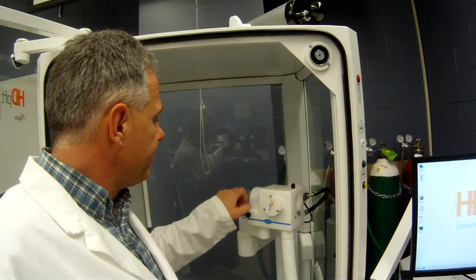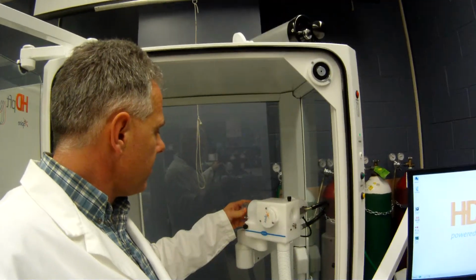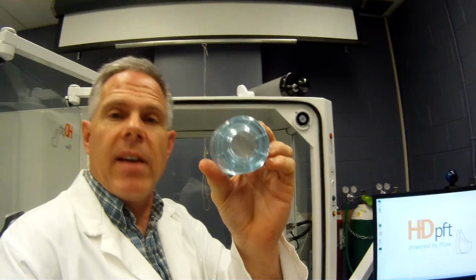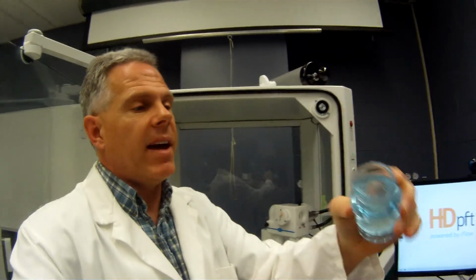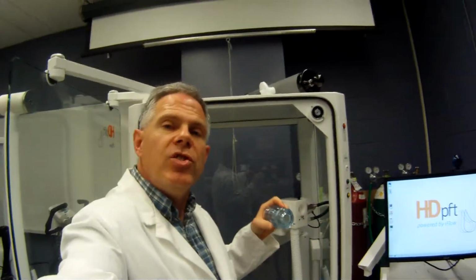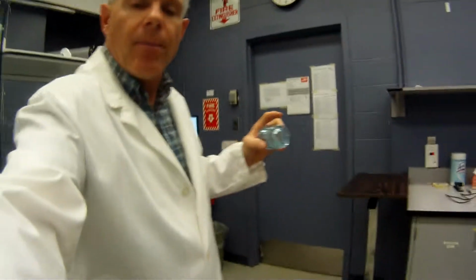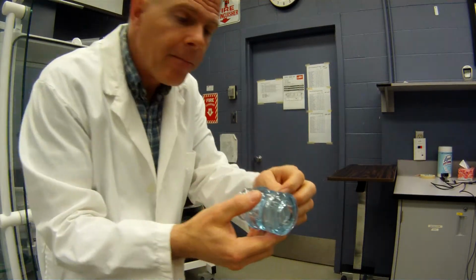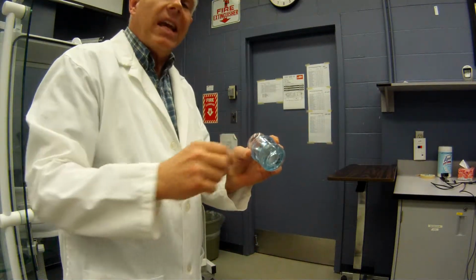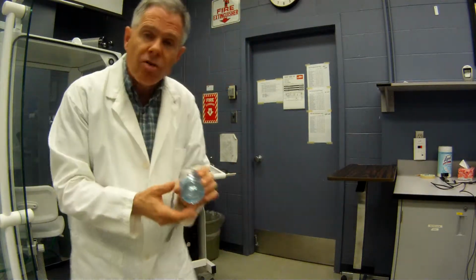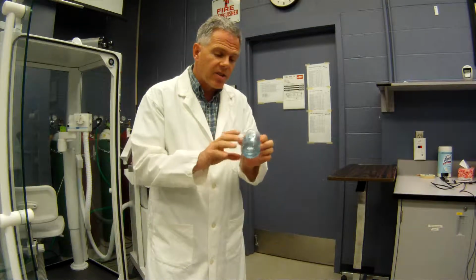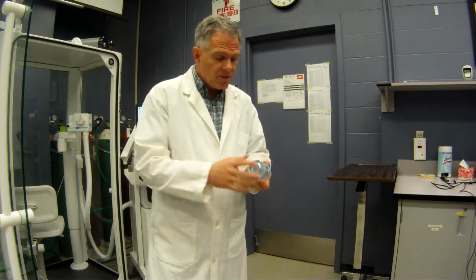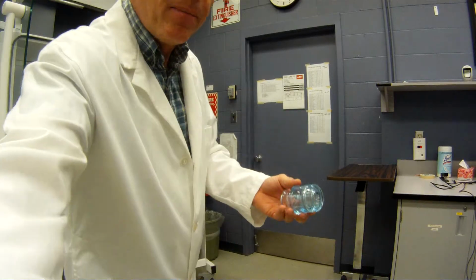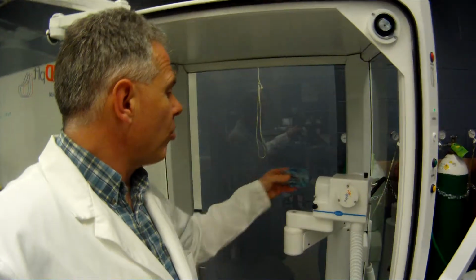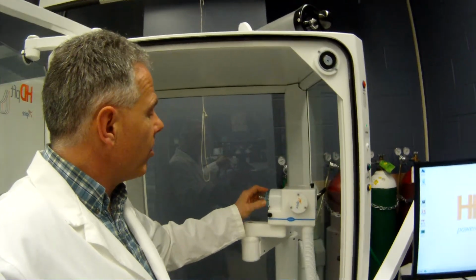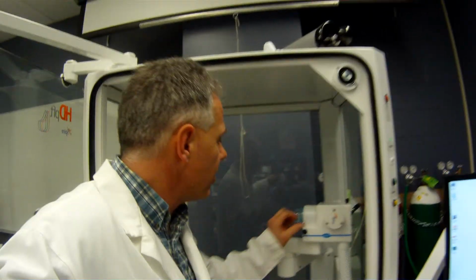Okay, so the heart of this unit is right here. This is our pneumotach, all right, and the way this one works is that we have a screen type pneumotach. So you can see that there's a little screen inside there and these little holes across here. So what this unit does is it measures the pressures across this screen and translates those pressures into a flow. And if we know the duration of the flow, calculated probably about once every millisecond or so with this device, we can measure the volumes. So that's how that works. So this little plastic piece here just fits right inside, and the actual connectors to the pneumotach go down into the computer, and the pressure transducers are down here, just housed in this unit right here.